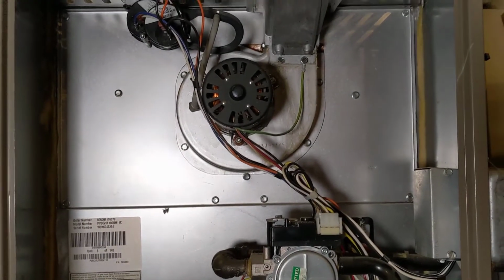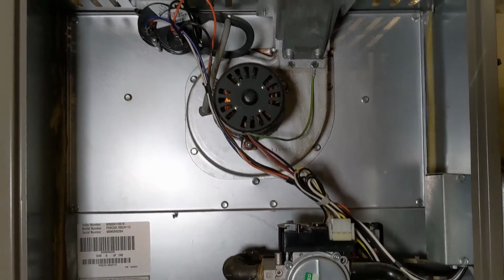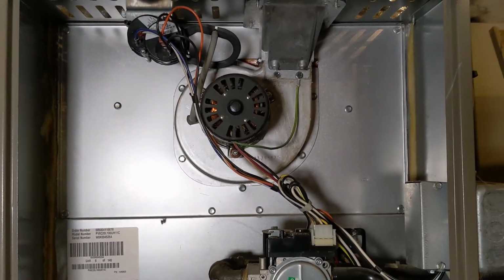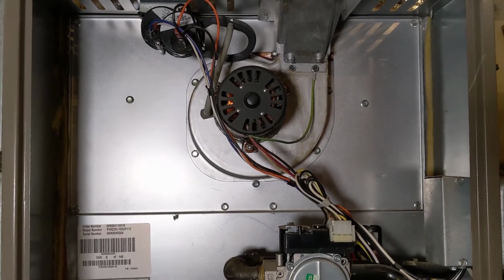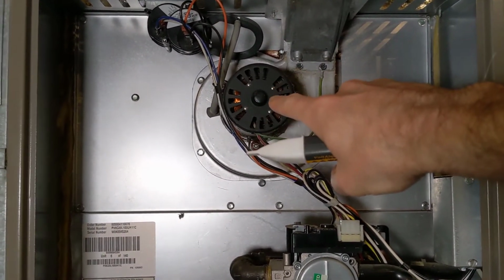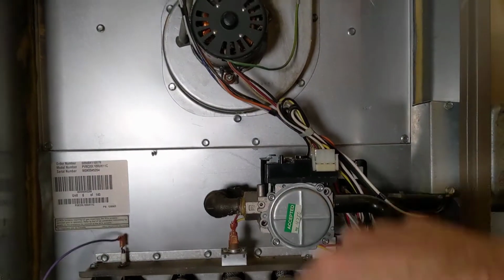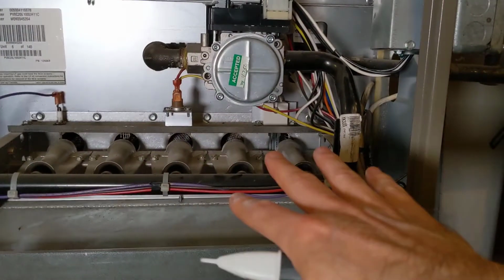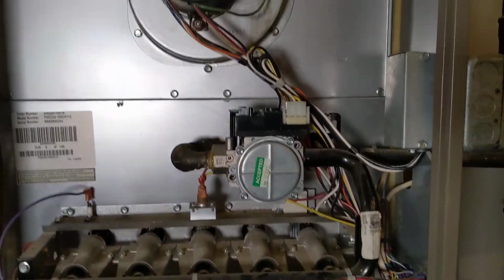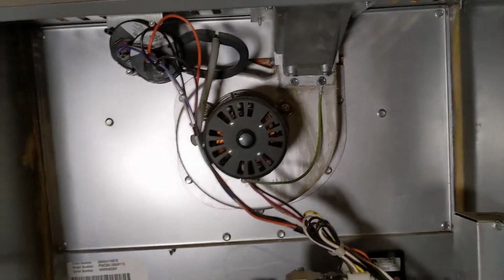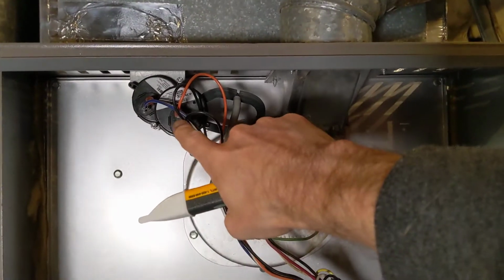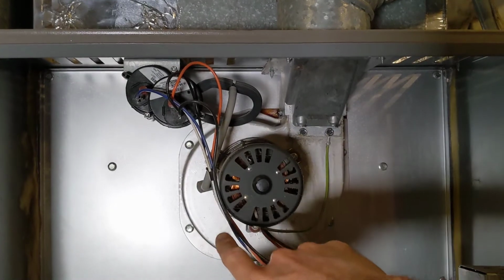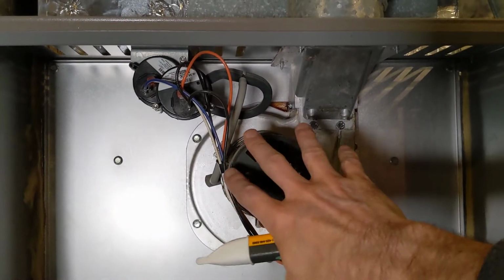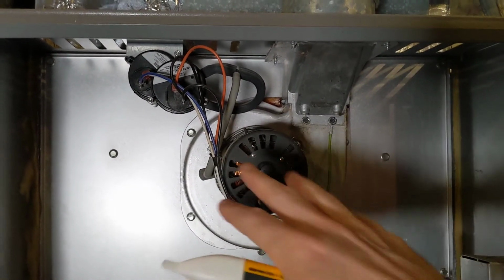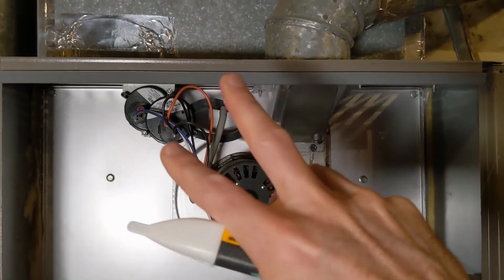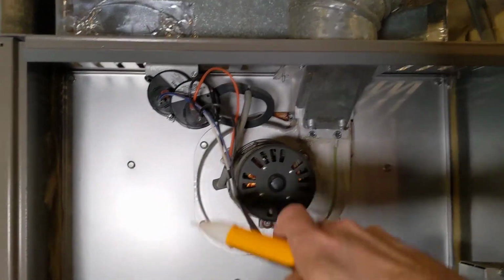Not a very common problem. Usually these inducer motors do last the life of the furnace, but I certainly have seen it before. So now let's say this motor starts up, but nothing else happens. We don't get flame or anything else happens. The typical problem there could be that the draft switch is not closing to prove to the board that this thing is creating a draft. So there's two potential problems there.